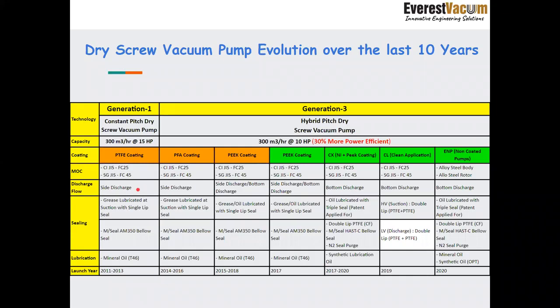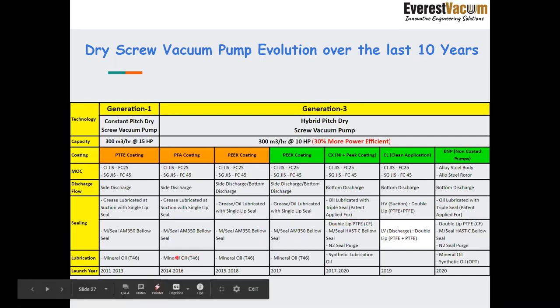Coming to Generation 1 pumps, they were side discharge pumps, Gen 2 as well. Now from Gen 3, they have come out to be bottom discharge pumps. So there were many issues in Gen 1 and Gen 2 pumps of pump blockage at the discharge, which led to their failure. Now we have ensured that the discharge remains free. That has been done directly towards the bottom under gravity flow. So this has been the transition over the last 10 years.